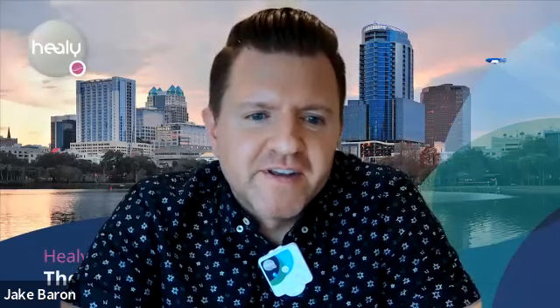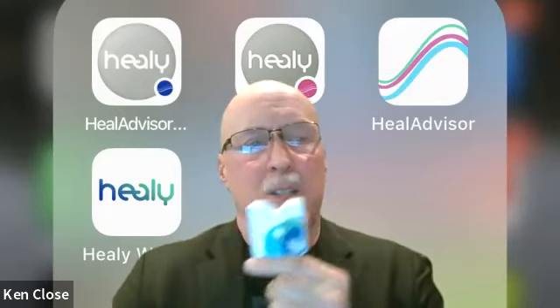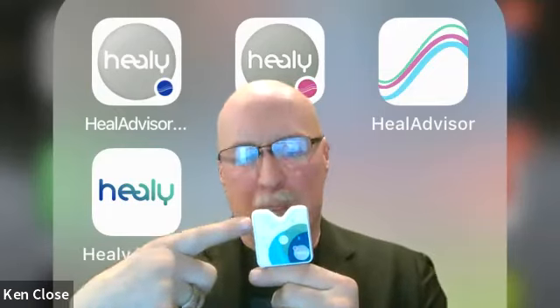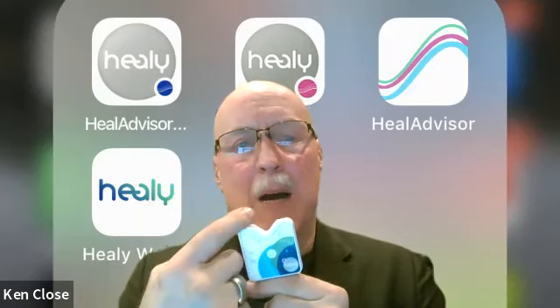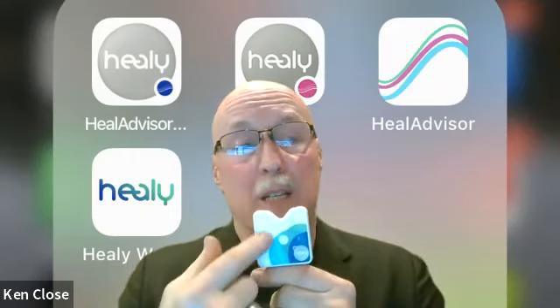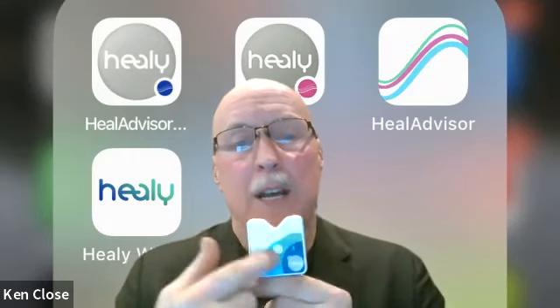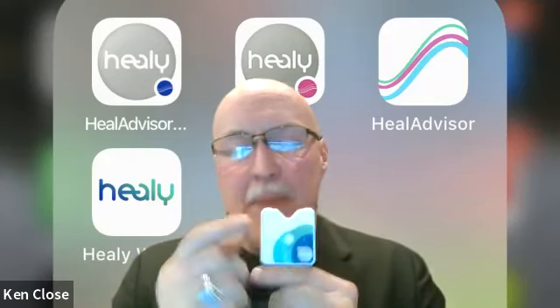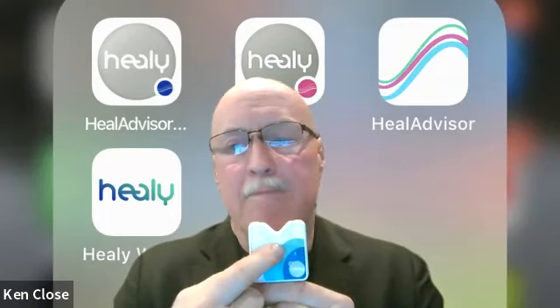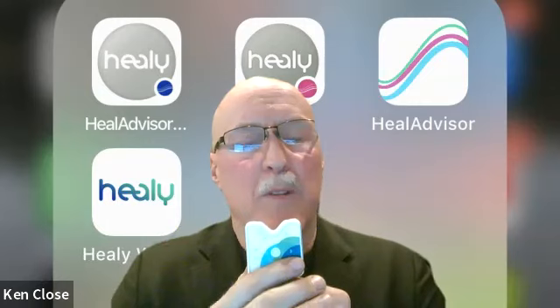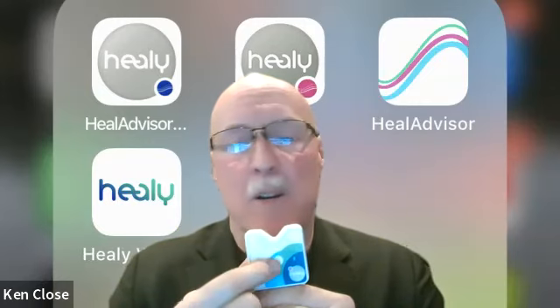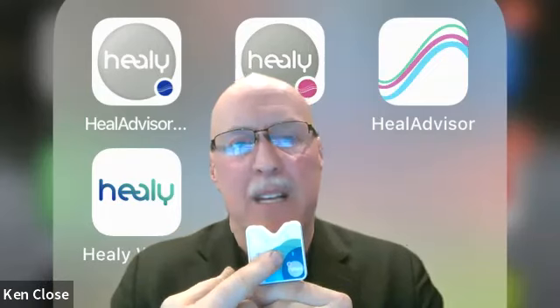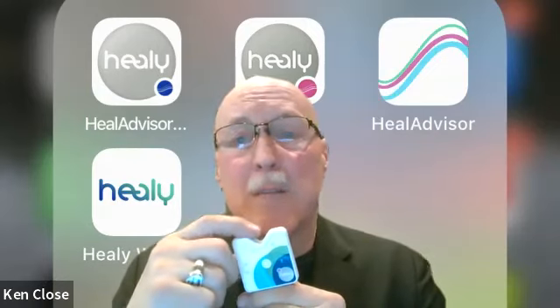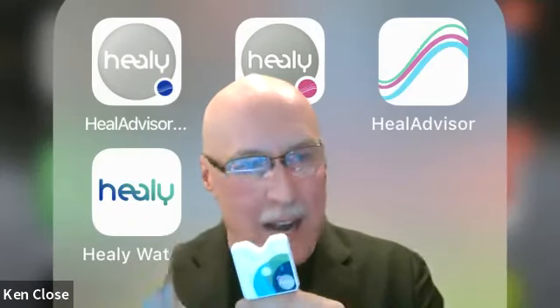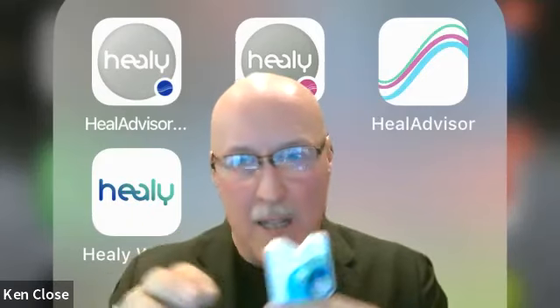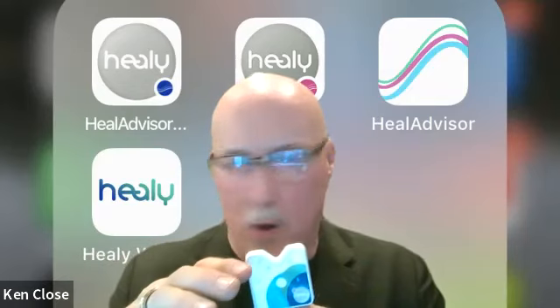And so let me give you a little clarity. This is built as a class 2 medical device. The way that it's engineered in all of the aspects also plays a part of the qualification for a medical device. In other words, a medical device that is used without supervision, without a practitioner, has to have fail safes built in. In other words, you're not supposed to plug the device into a wall outlet, 120 volts in the US, up to 20 amps, which is more than enough to fry you.